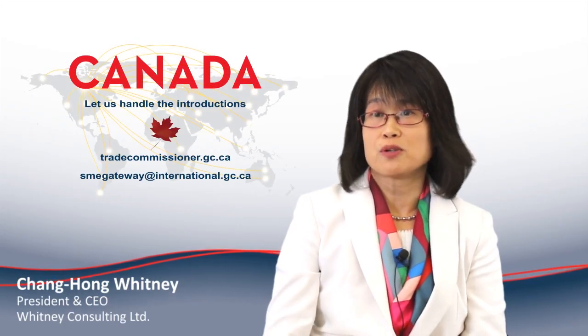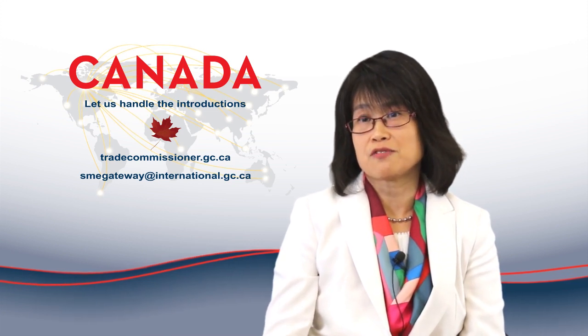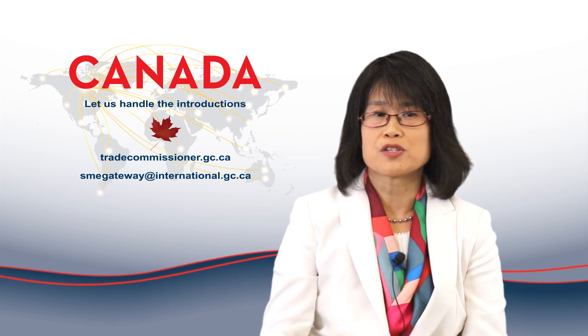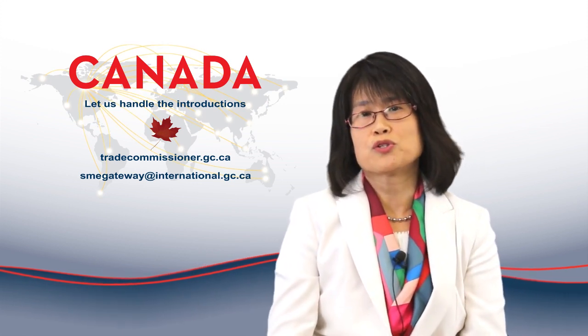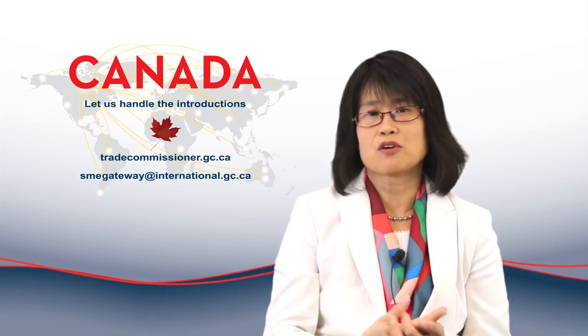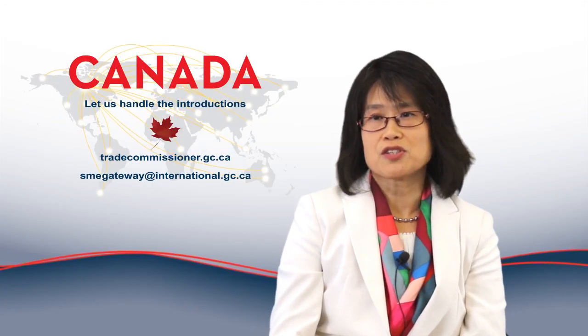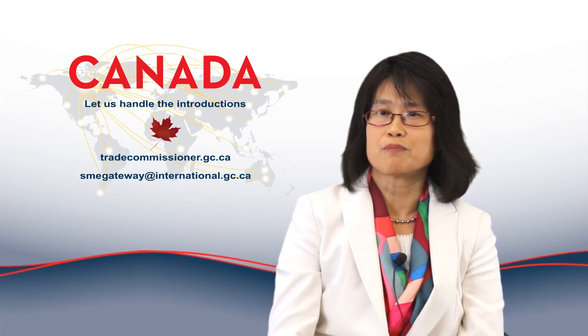Class 1, the simplest and least risky product category in China, has been relaxed by CFDA — not requiring a lengthy registration, just documentation. We prepare a set of documents with product information and technical details and file them. Typically, Class 1 device registration can be done within two to three months. Class 1 filing also does not require a CFDA registration fee and has no expiration date, so there are no renewals — a lot of advantages in having a Class 1 device in your product mix.